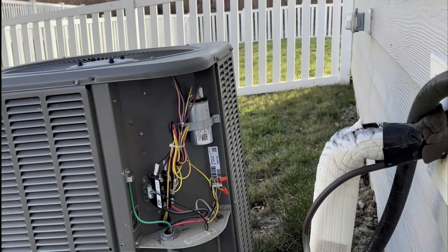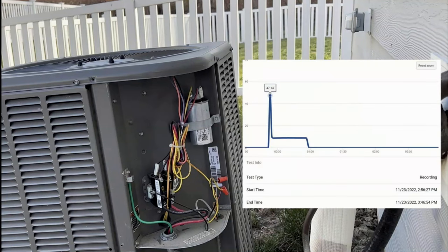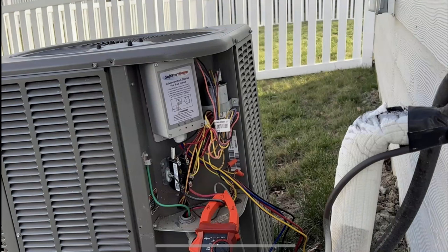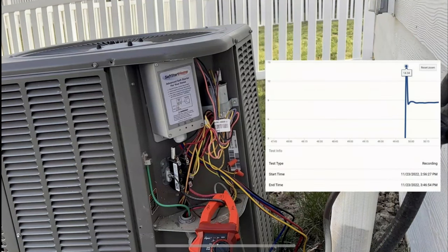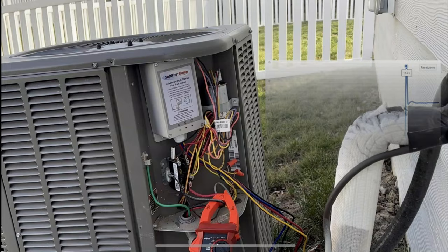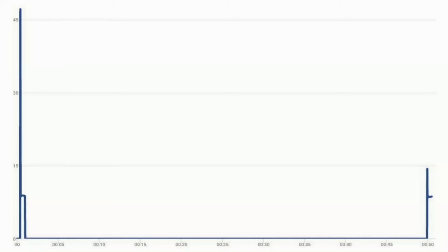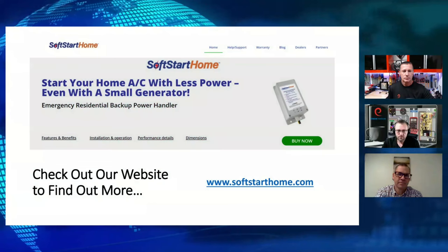Okay, so conclusion: without the soft start, it had a peak inrush of 47.14 amps, and with the soft start, we had a peak inrush of 14.34. That's a pretty significant difference. Definitely would be substantial if we had this on a backup power source, particularly with a generator startup.